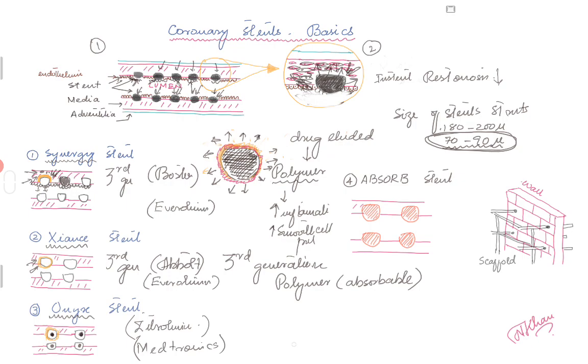What's neat about the Onyx stent is they've really crafted that stent in a very nice way. They made the inside of the stent strut hollow, and inside that hollow stent strut they've put an alloy which is radiopaque. What does that achieve? If you're putting a stent in somebody who's very obese with a lot of body mass, you want to really see the stent. As you go down on the stent strut size, it becomes very hard to see the stent, especially when placing stents. Onyx has put this alloy which is radiopaque inside the lumen of the stent strut, and that makes it more radiopaque so you can see it on the angiogram.